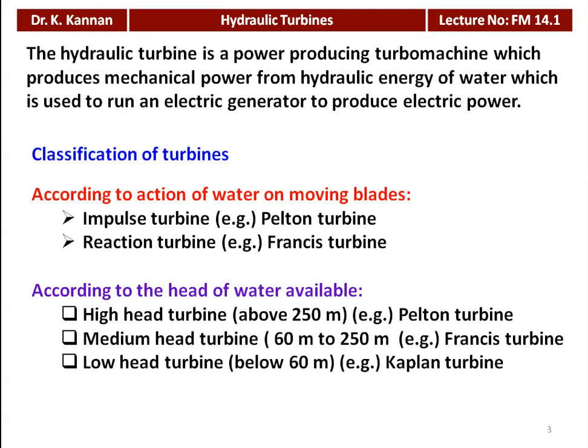According to the head of water available: a high head turbine has a head above 250 meters — for high head applications we use the Pelton turbine. A medium head turbine has a head of 60 to 250 meters — we use the Francis turbine. For a low head turbine, when the head is less than 60 meters, we use the Kaplan turbine.